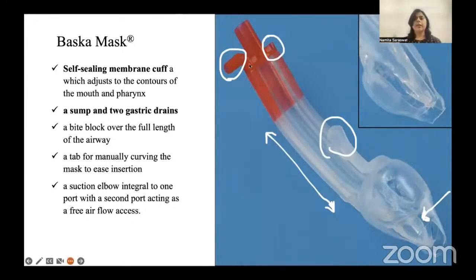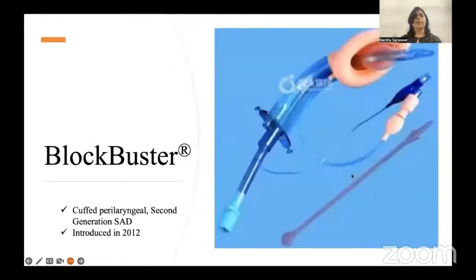So if you have to describe this device, the Baska mask also has a unique feature of two gastric tubes. You can see one here and the other one is here. This is an airway tube. Throughout the airway tube, an integral bite block is available, which provides it rigidity. And there is a tab. You can see this tab is there, which is manually curved, and it provides manual curving of the mask and serves as an aid for easy insertion. Here you can see there is a suction elbow integral to one of the ports, and the other gastric port is open to the air. So this is how you can describe the Baska mask.